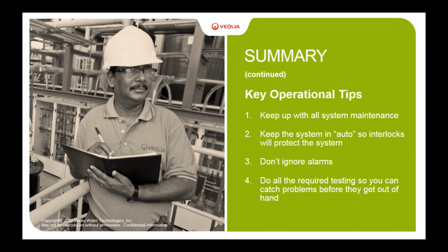That's also why you want to keep your interlocks and your alarm systems up to date. If you have a nuisance alarm that you're constantly ignoring, try to figure out, with your IT department or by calling us if we supply the system, how we can change those interlocks and alarms. They are there for a reason. They do help. They should typically be pretty simple to change the set points on so they don't become nuisance alarms or nuisance interlocks. Nobody likes them. When we're commissioning and starting up systems, we try to work through all of those. But when you're out in the real world, some interlocks that look great on paper, when the process engineer is in the real world, don't work, and we need to be able to change them so you don't have those issues.